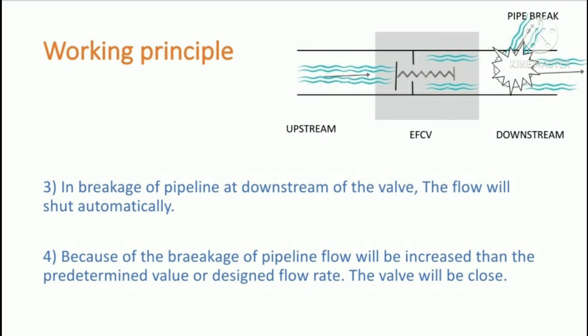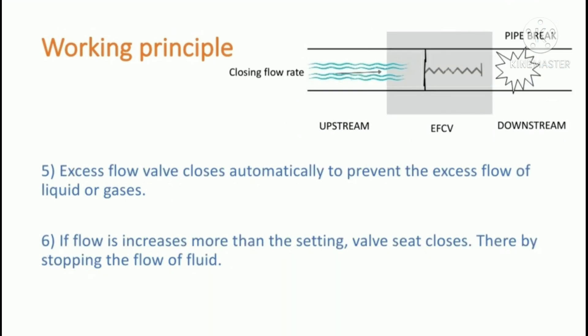if the line breaks at downstream and fluid flows out, the valve will shut automatically because the flow will increase, and because of the increased flow force on the spring, it will shut automatically. The valve is now shown as fully closed.